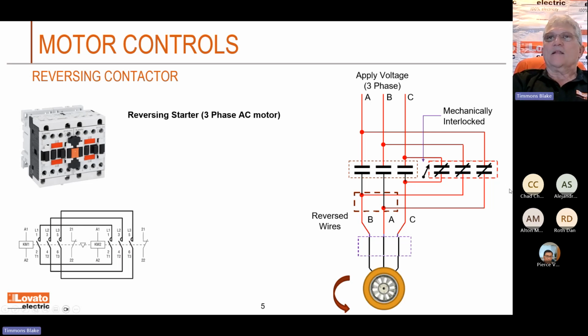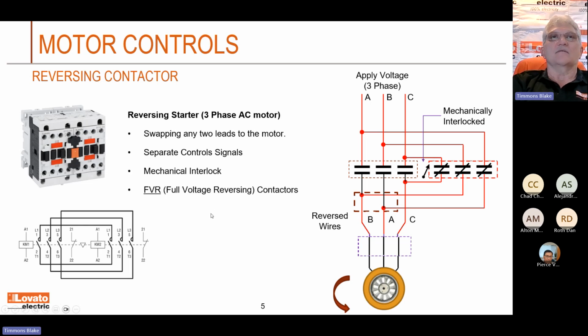Now, you'll see that little purple box down there. I left it blank right now because that's where your motor overloads are going to go. Here we go. Now I'm telling you about the separate mechanical interlock. This terminology is used a lot for a full voltage reversing contactor: FVR. When you see that on a quote or request, that's what they're talking about. And then there's your motor overloads I talked about. That's a symbol for the heaters, thermals.